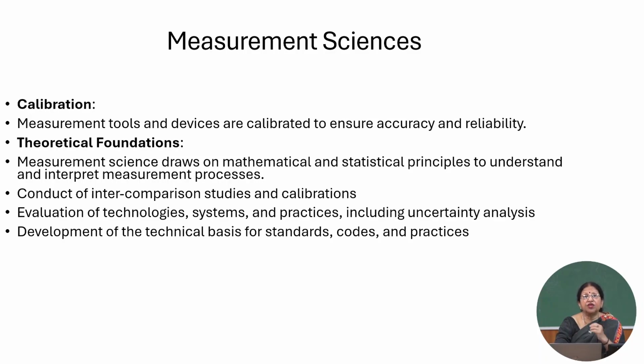Therefore, repeatedly we mention to all the new research scholars that keep doing your calibrations for the instruments, even instruments like FTIR, UV-Vis, they need to be calibrated from time to time. The machine is provided with calibration samples so that one can check whether the machine is working properly or does it need some kind of calibration or validation in the process. Otherwise, these can become very, very different, and it can cause many mistakes in the final analysis when the research scholar goes to analyze it.